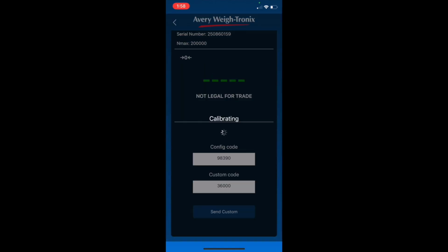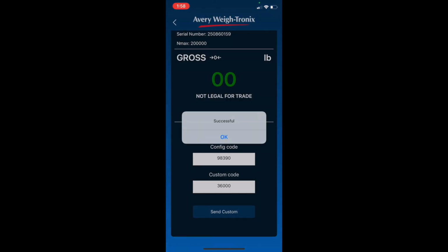And then to figure the adjustment, you'll take the actual weight divided by the incorrect weight and take whatever that error percentage ends up being. So if it's 1.01 or 0.98, you take that times 36,000 and adjust up or adjust down accordingly.